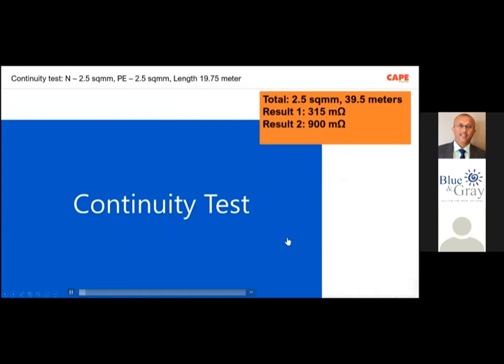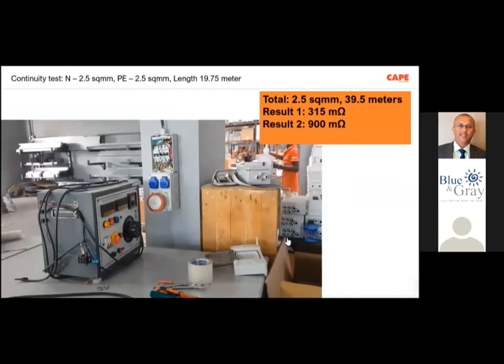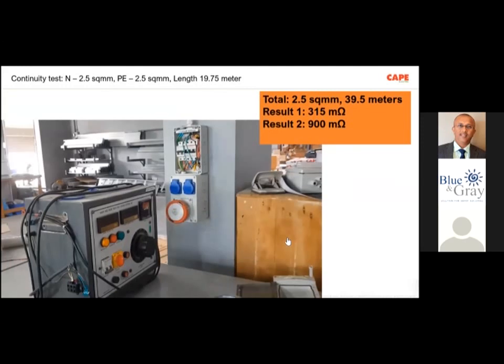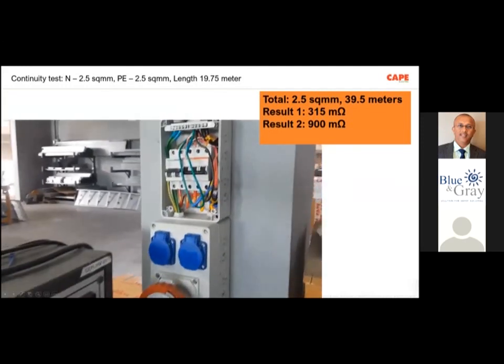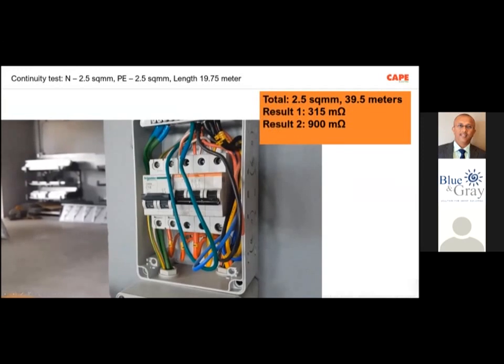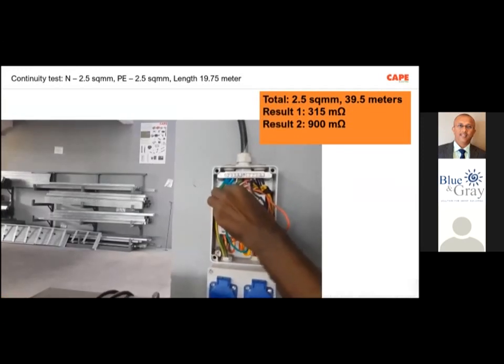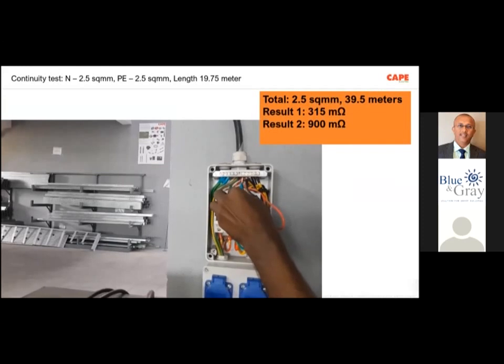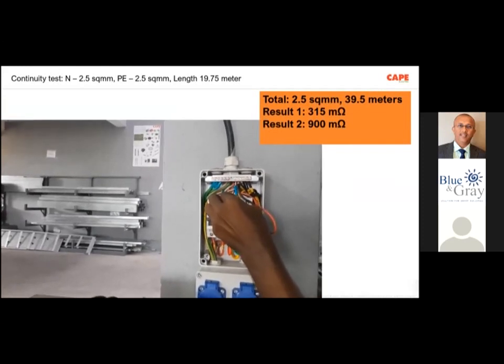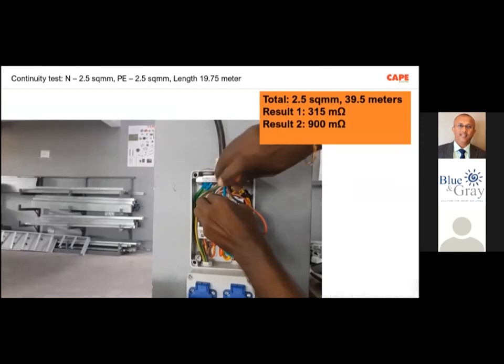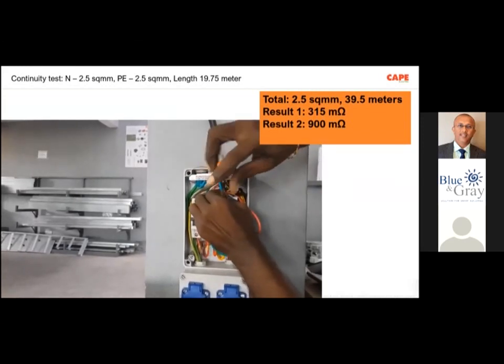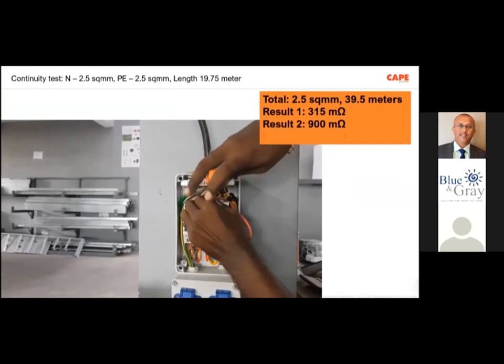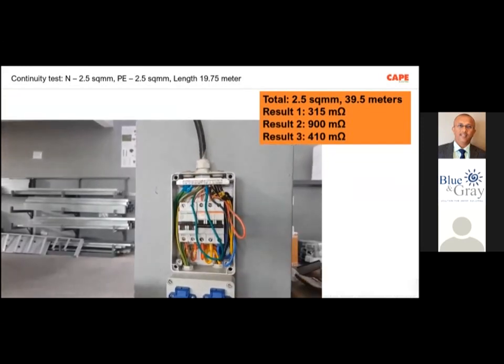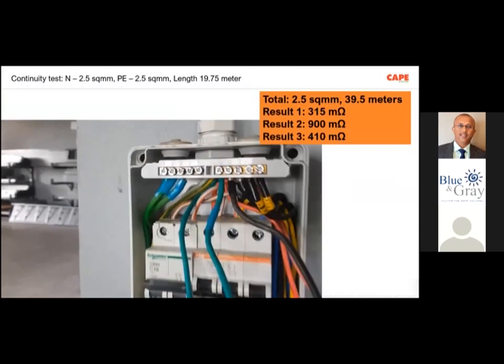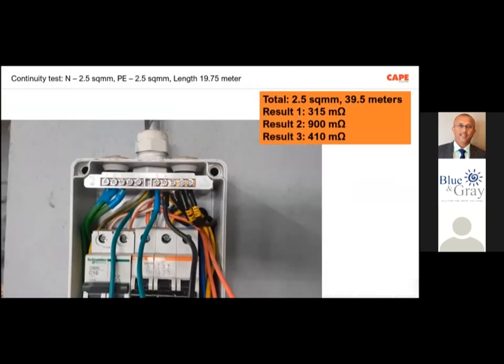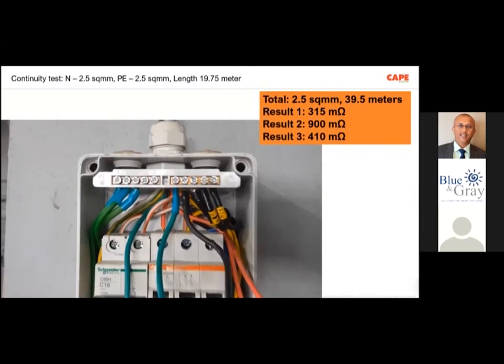So we are going to measure the resistance of 2.5 square millimeter wire, about 20 meters, 19.75 meters in each length, so totally 39.5 meters. The wires are shorted at one end. Then we use 3 meters just to explain that the accuracy of the meter is equally important. Here we shorted the neutral and earth together temporarily, because this is a test which has to be done in off condition.